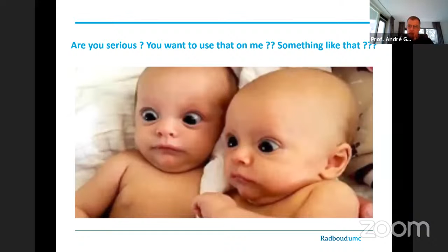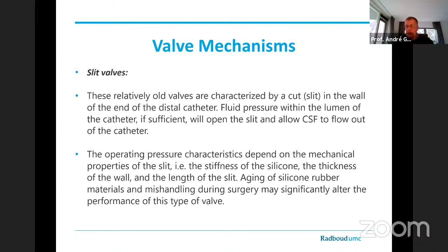So let's look at what we have: 3 different types of valve mechanism. The slit valve, the famous old Holter and Pudenz slit valve. That's a slit in the catheter, and it will only let drops out when the fluid pressure in the lumen of the catheter is high enough. The opening pressure depends on the stiffness of the silicone, the thickness of the wall, and of course also the length of the slit. The problem with slit valves, please remember this, is that aging of the silicone rubber and also tampering and manipulating it during the surgery absolutely alter the performance of this type of valve. So it is very uncertain what type of pressure management and differential pressure is really inserted here. But these are still available.